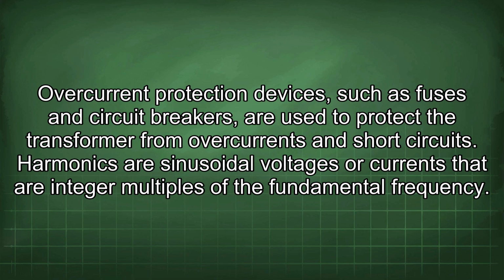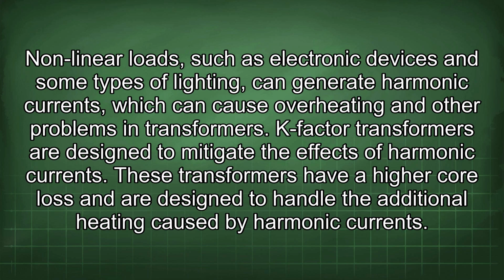Harmonics are sinusoidal voltages or currents that are integer multiples of the fundamental frequency. Nonlinear loads, such as electronic devices and some types of lighting, can generate harmonic currents, which can cause overheating and other problems in transformers. K-factor transformers are designed to mitigate the effects of harmonic currents. These transformers have a higher core loss and are designed to handle the additional heating caused by harmonic currents.